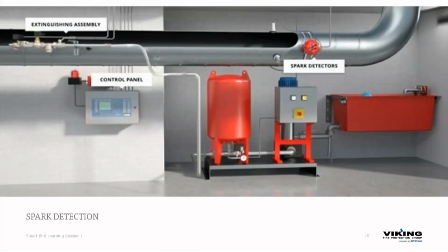Here's a quick little diagram showing spark detection in ductwork and how it works. If you can imagine your ember is floating down your ductwork right here. It gets picked up by these 2 UV detectors. Alarms go off, the process shuts down, and water gets directed to your extinguishing assembly. That piece of ember will keep floating and it'll hit a wall of water inside the ductwork. You'll know because your process shuts down. Your ductwork is full of water and pouring all over the floor, and your alarms are going off. But nobody died, though you have a mess on your hands. I've been in a facility when that happened.